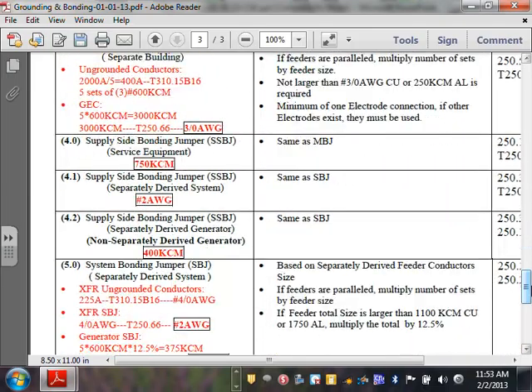Okay, here's 4.2. Now remember, we're on the generator side. 4.2 is called supply side bonding jumper, separately derived generator. And how do we size it? We size it based on the same thing, the system bonding jumper. And in this case, it happens to be a 400 kcmil. So that's also a supply side bonding jumper.